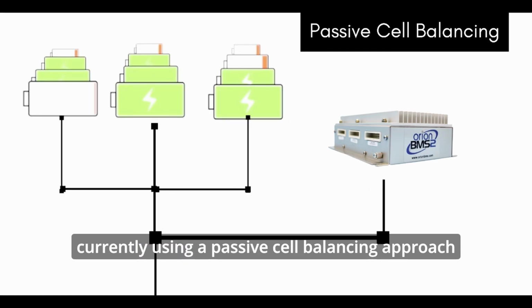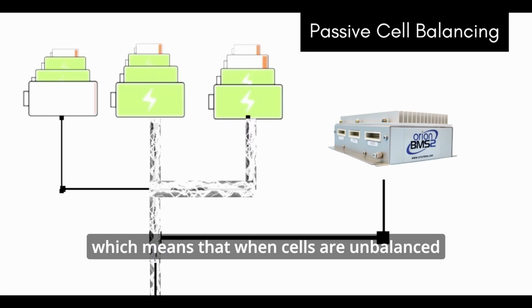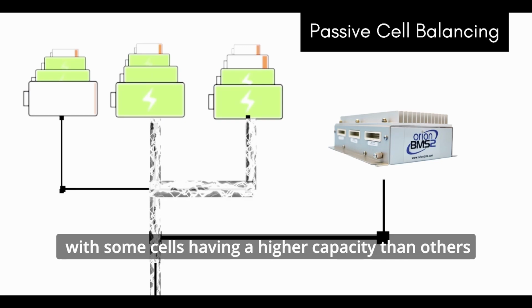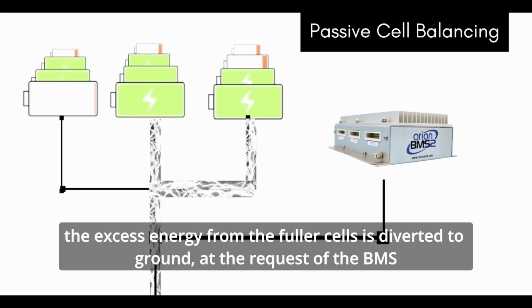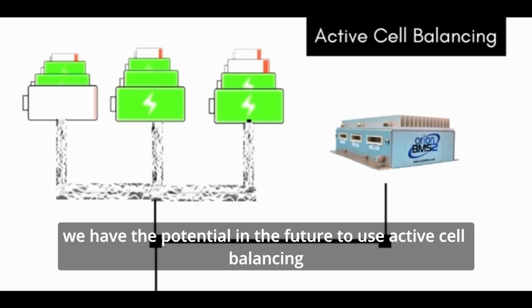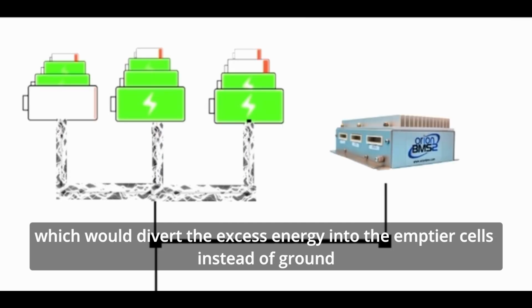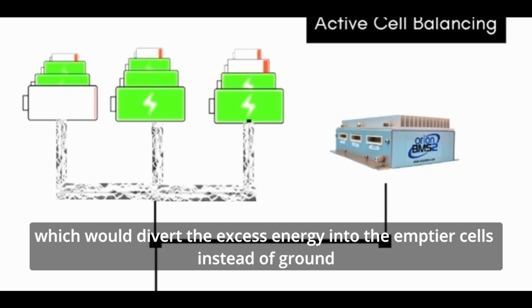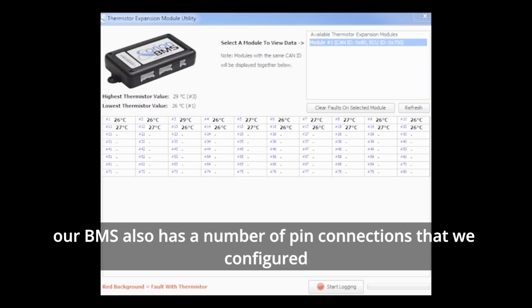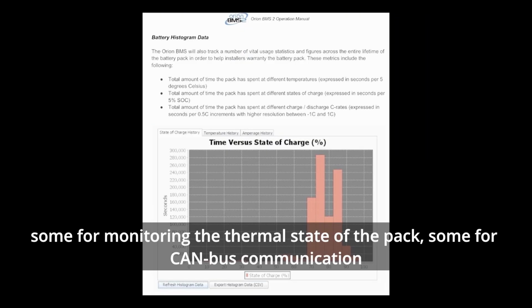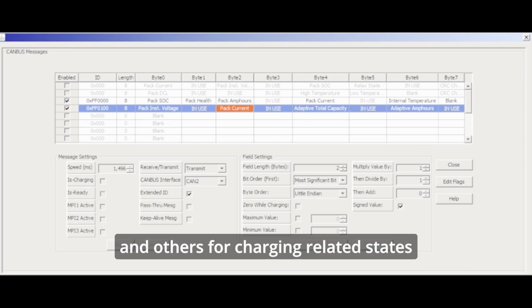We are currently using a passive cell balancing approach, which means that when cells are unbalanced, with some having higher capacity than others, the excess energy from the fuller cells is diverted to ground at the request of the BMS. We have the potential in the future to use active cell balancing, which would divert the excess energy into the emptier cells instead of ground. Our BMS also has a number of pin connections that we configured, some for monitoring the thermal state of the pack, some for CAN bus communication, and others for charging related states.